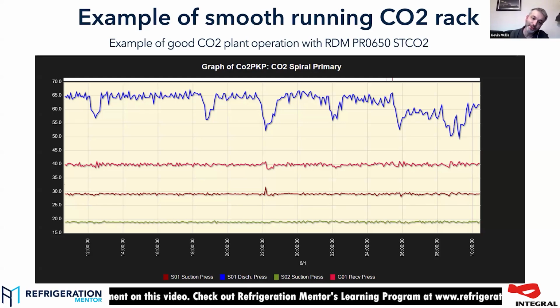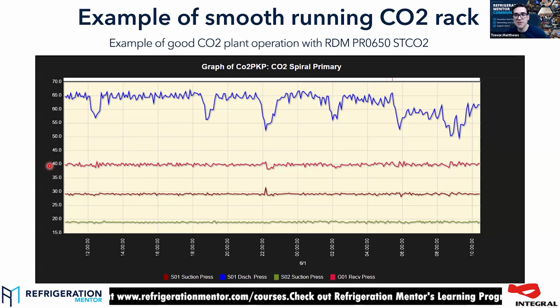So SO1 generally on RDM is your medium temperature. SO2 is generally your low temperature. So you can see your 2 suction lines pretty stable and your receiver/flash tank pressure pretty stable. The system runs with a decent amount of load on it all the time because it's production. So it's beautiful. Like it's running nice and straight.